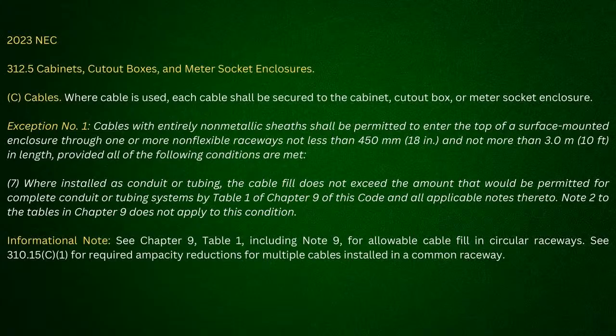Now, one of the things they kept pointing to was 312.5(C), and they were looking at exception number 1, and item number 7. One thing I want to point out is that 312.5(C), where it talks about cables, says where cable is used, each cable shall be secured to the cabinet, cutout box, or meter socket enclosure. Then if you come down to 7, it says where installed as conduit or tubing, the cable fill does not exceed the amount that would be permitted for a complete conduit or tubing system by what? Chapter 9, Table 1. Yes, so it has to be a complete conduit or tubing system, and all the applicable notes, except what? Note 2.